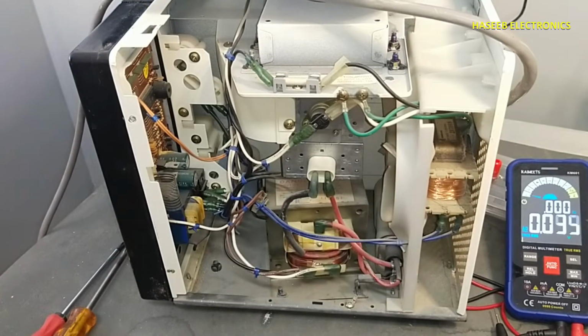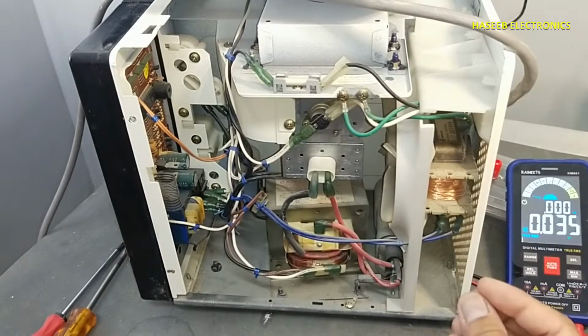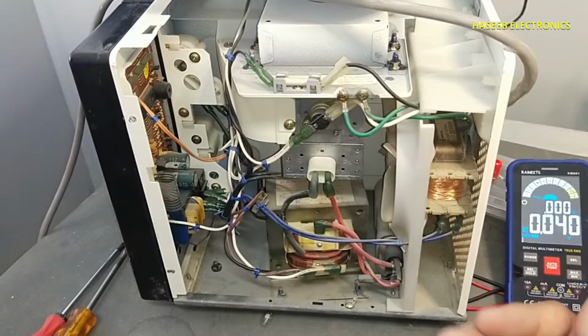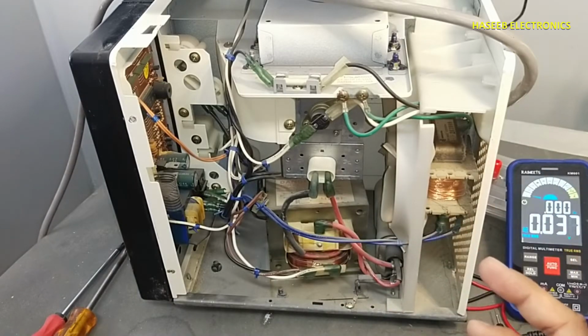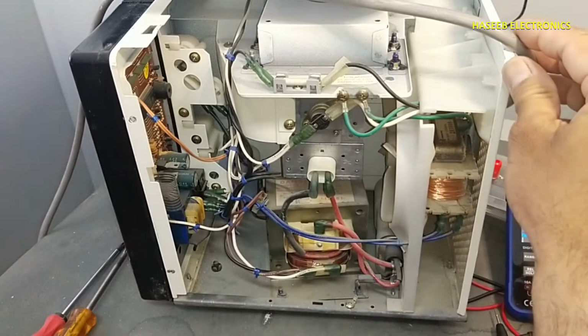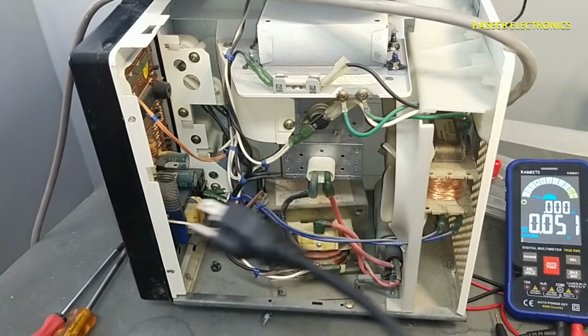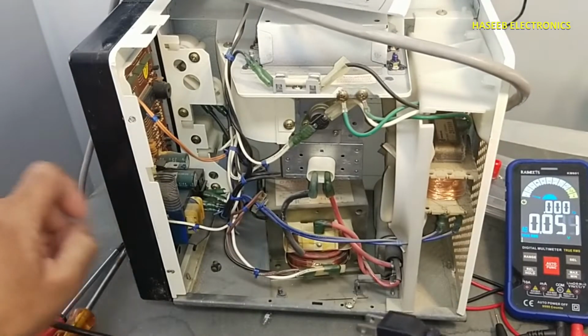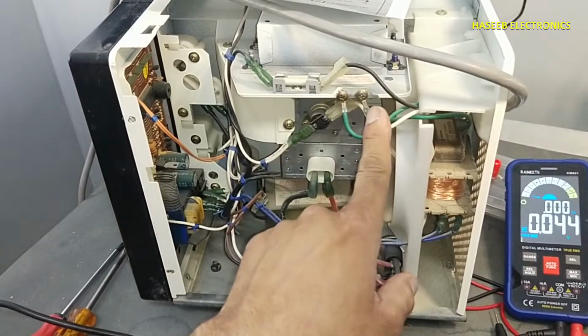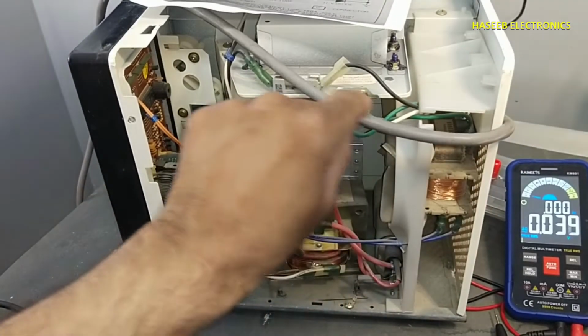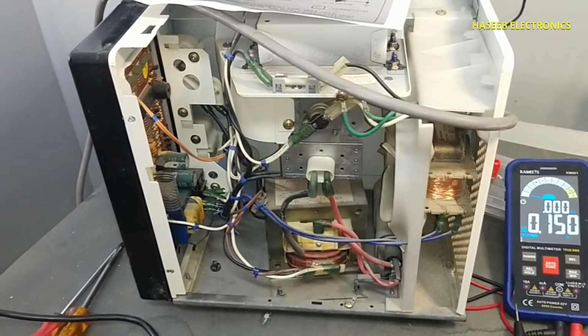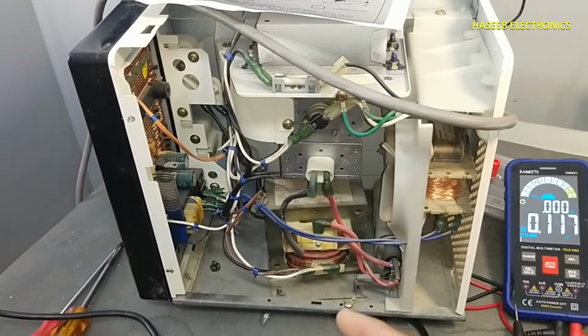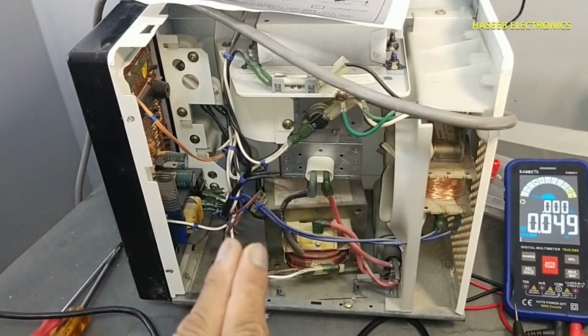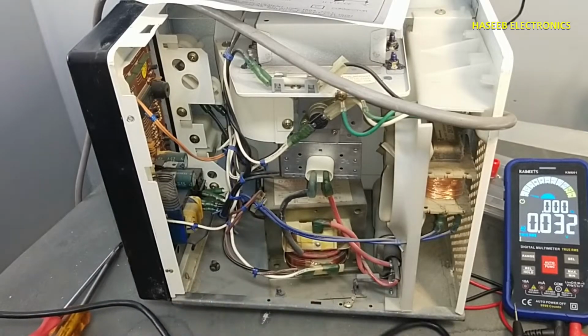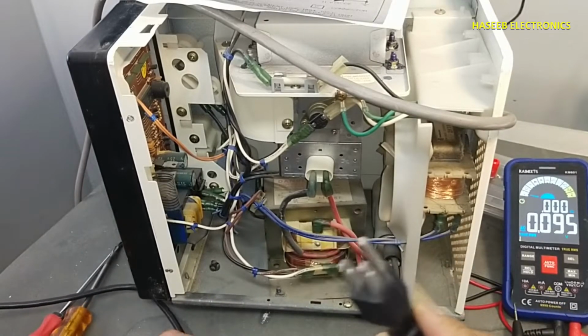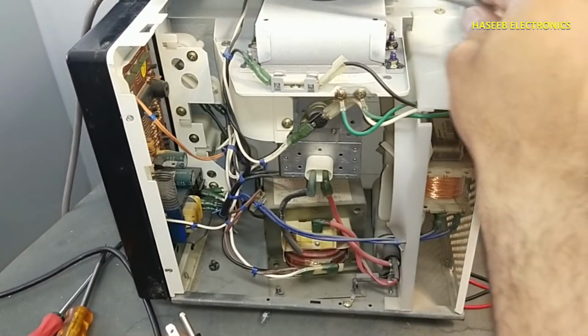Now the second condition: when we apply power, the main circuit breaker trips off. That is due to a short circuit. Might be from this point to this point, this cable is short circuit internally. Its internal insulation is perished, and its metallic wires are touching together. It can cause the fuse to trip out. At that time we need to replace this wire.